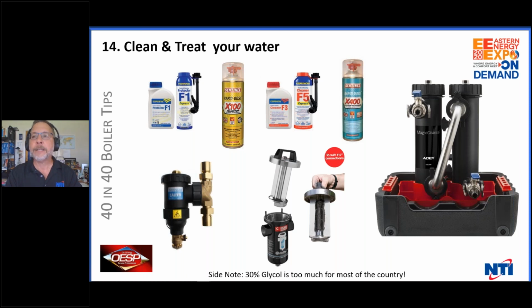After you fill it, put in your protector. Your F1, your X400, your number 1, whatever you're going to use, put the protector in. However many cans you used of the emulsifier, you put into the protector. And if you're like me and you like belts and suspenders, well, I don't wear them that way, but I like to make sure I have double safety. Use a magnetic filter on the return. I've seen these on systems that have absolutely no cast iron except for the pumps in them. Everything else is PEX and brass and copper and stainless, and still after a year have all the collection of all the magnetite on the magnet.